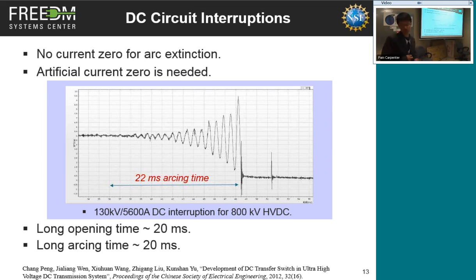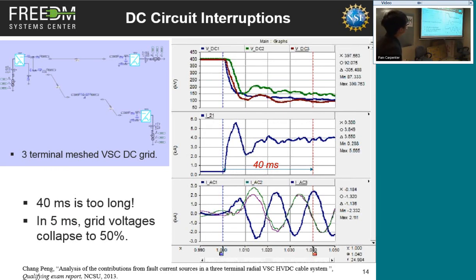The requirements will be different. And why is that? Let's look at these three. This is a DC grid based on voltage source converters. I made a mistake here because this is apparently not a mesh system. This is a radial system, but never mind. Let's look at what happens if there's a fault in this voltage source-based DC grid. I have implemented a fault here. This is a simulation in PSCAD, by the way. It has all those voltage source converters, those switching functions in this model, so it should be very accurate. And it also has a transmission line model, so all these transients should be very accurate. We have a 3-terminal system here, and some fault happens here.